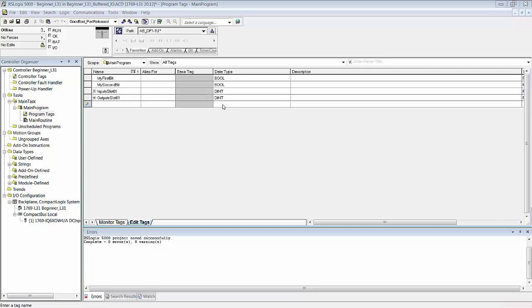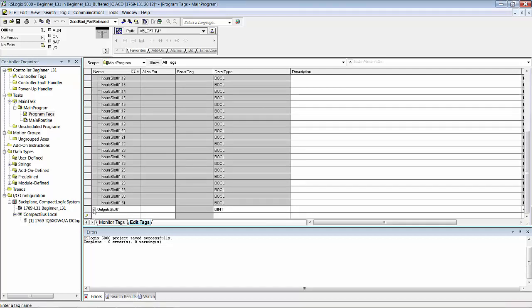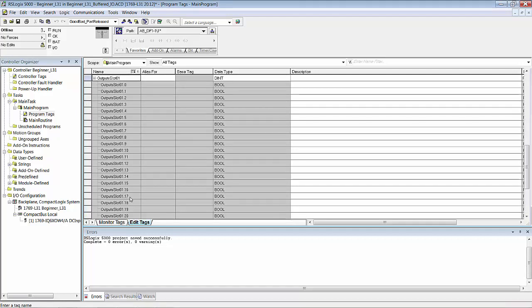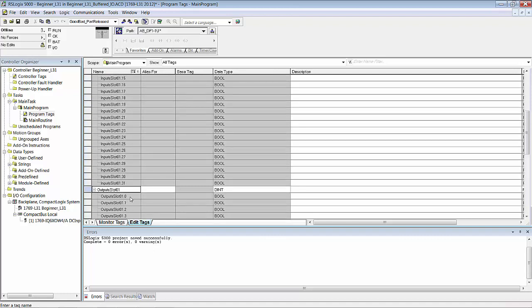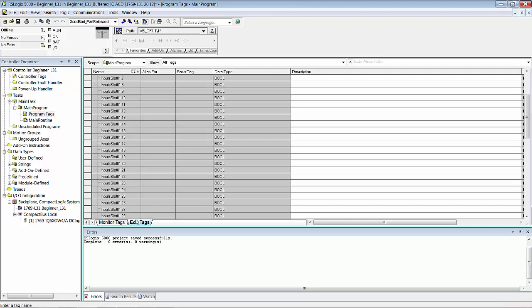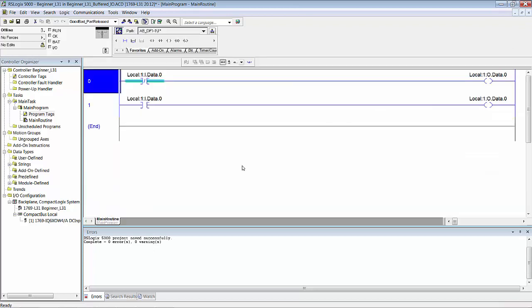We'll just make them dints. Keep in mind that each of these is a 32-bit double integer; all bits are there in memory and they are all accessible read and write. However, we have reserved that space in memory for access to just six bits from one of the dints and four bits from the other. So I had you expand these. Unfortunately you can't see both simultaneously because they are dints. I had you add two new rungs. I had you add one at the beginning.